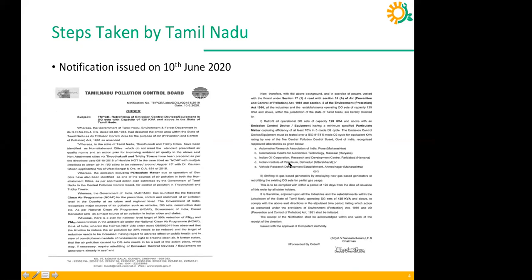So Tamil Nadu made it even clearer that now in the state of Tamil Nadu, if you have a 125 kVA and above, either retrofit it, and if you are retrofitting it, you have to adopt an emission control technology which gives you minimum 70% reduction from the current levels of your PM, particulate matter emission, and that retrofit should be tested from any one of the 5 CPCB recognized labs under this particular standard for equivalent kVA. I'm stressing the need on these particular words because this is the entire premise on which the policy is laid out, and this is the entire premise on which your selection criteria for a vendor should be based.